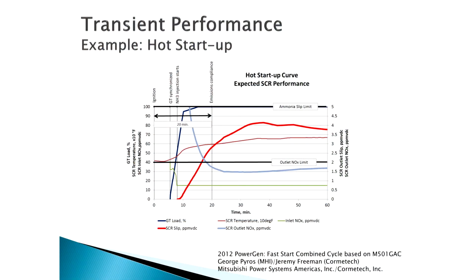And then there are the testing methodologies on top of that. We talked about, and I mentioned, CTM 027 for ammonia, and you start to look at how you contractually prove that your ammonia at 20 minutes is, in this case, less than 4 ppm. Well, CTM 027 is a 1-hour integrated sample. So how do you know where you are 20 minutes in versus 25 minutes in? The industry needs to figure out a way we can all agree on how to do this testing, because until you can agree on how it's going to be tested and measured, you're going to have trouble getting people willing to guarantee it. If you can't measure it, it's really hard to prove what you're doing.